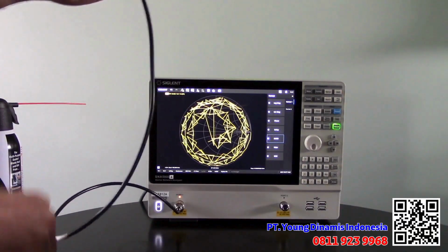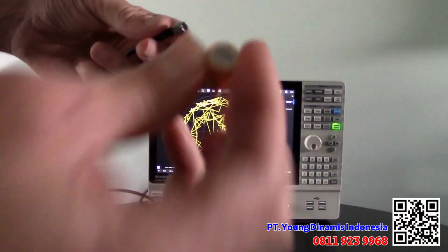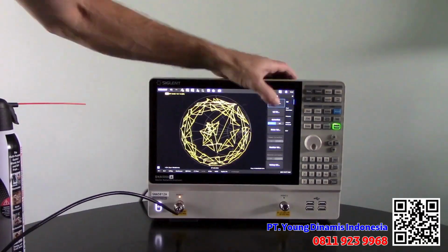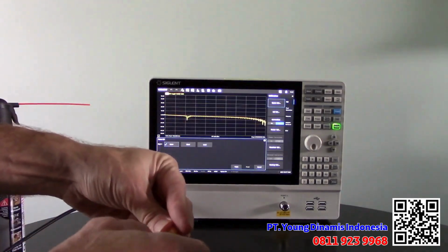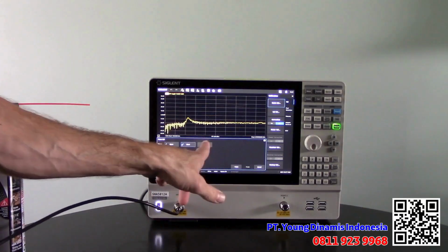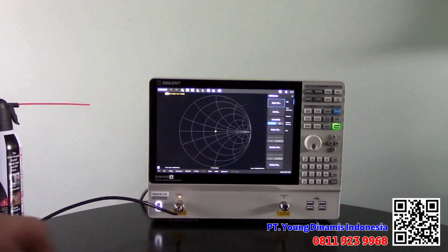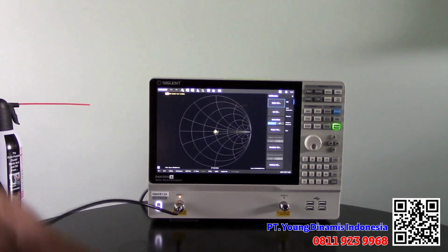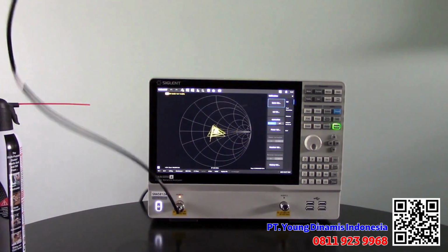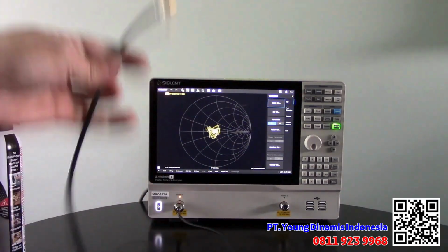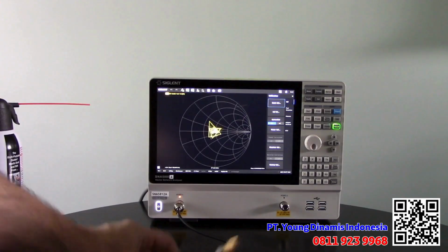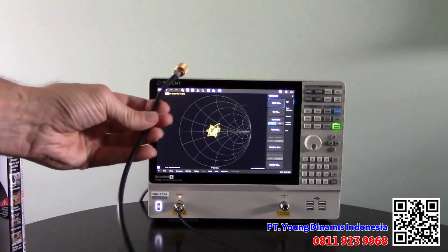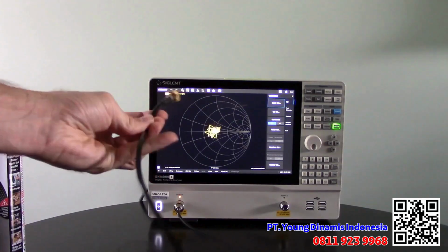So now let's connect the other cable, and we're going to see immediately that there is quite a bit of a difference on the Smith chart. Let's do the calibration very quickly. Short, open, load. And once we've finished that and accepted it, we can take a look. Now we've got that characteristic impedance in the center again, that's the 50 ohm point, but you'll see it's much bigger. And as we move the cable, you can see that there's quite a bit of instability, a lot of changes over time as we reposition that cable. And what that means, if we are to calibrate using this cable, any changes to that cable's position could very well change that reflected measurement, and that could be problematic for us as we go forward.